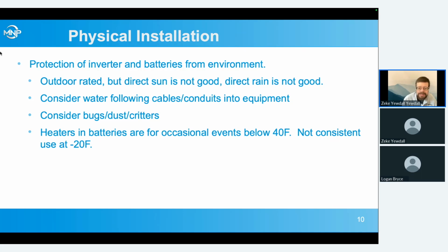Another thing to think about is the wall mount batteries have built-in heaters, and we've seen a lot of people that have taken that idea way past what its intended use was. They're intended for occasional events where we drop below 40 degrees. Say you're in a fairly mild climate where you might get down to 20 degrees a couple times a winter. That's probably fine for, say, an outdoor installation on the back wall of the house. Not like in an unheated equipment room in a Montana mountain telecom site where it's 20 below for weeks on end. And we've seen situations like that where it's just not up to doing something like that.